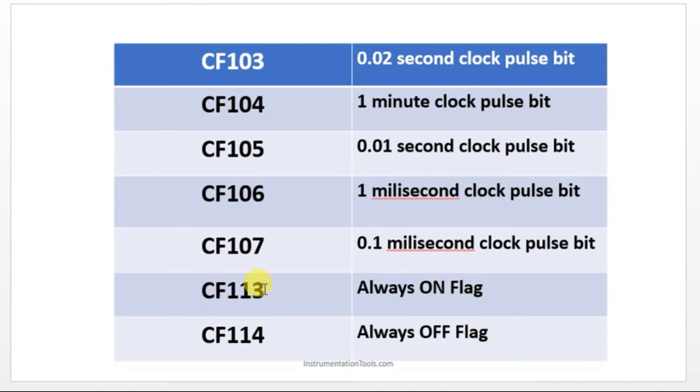We also have always on flag and always off flag, which means whenever the CPU is on, this flag will be continuously on. You can make use of this flag to turn on some output. Whenever your PLC is on, you can able to turn on an output using this flag. There is no need to connect any memory coil or any other input address. You can directly use this flag to turn on that particular output. And this is for always off flag.